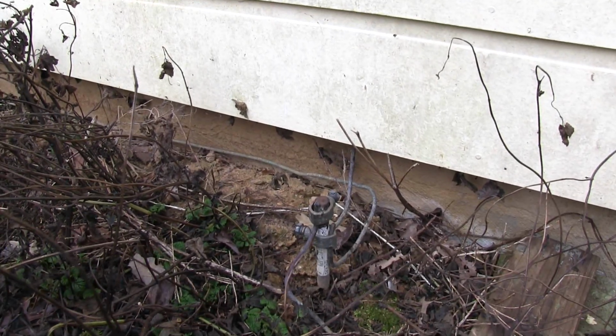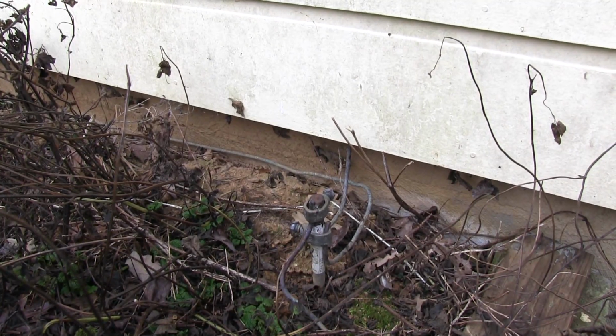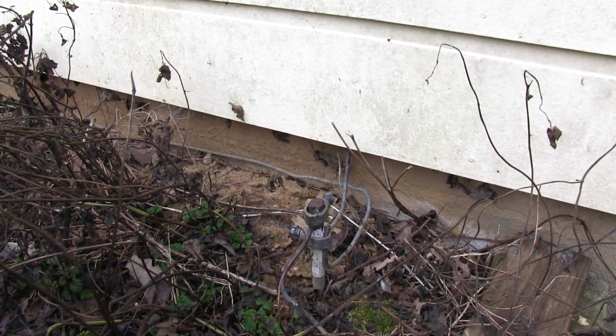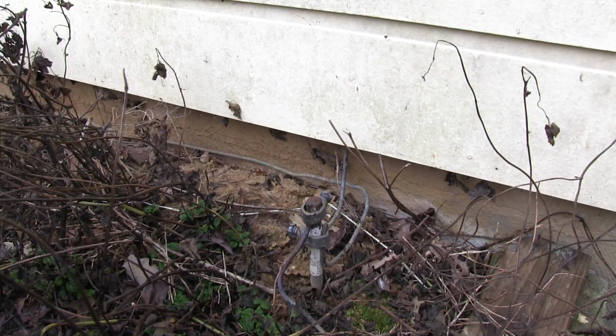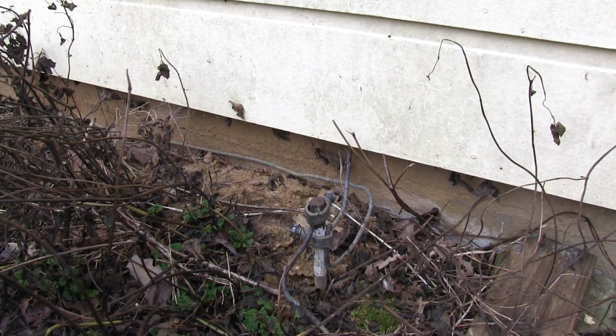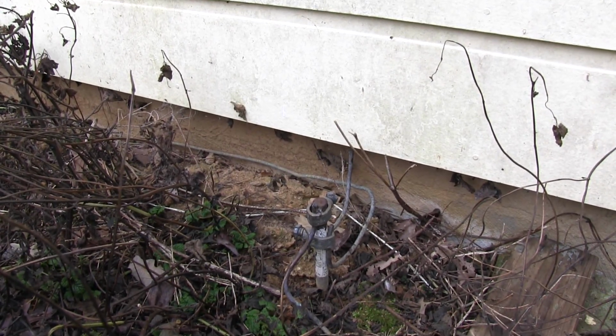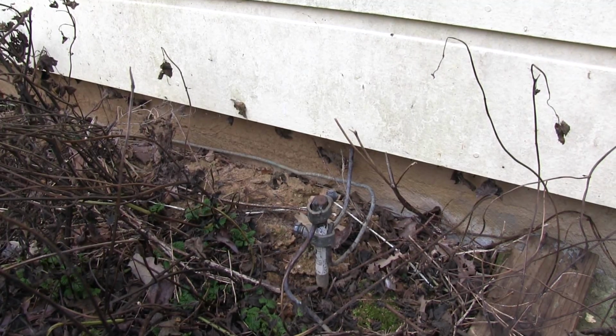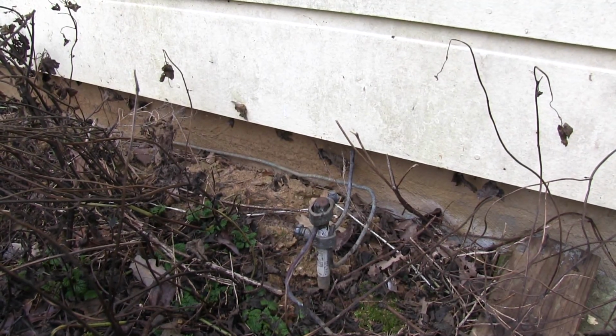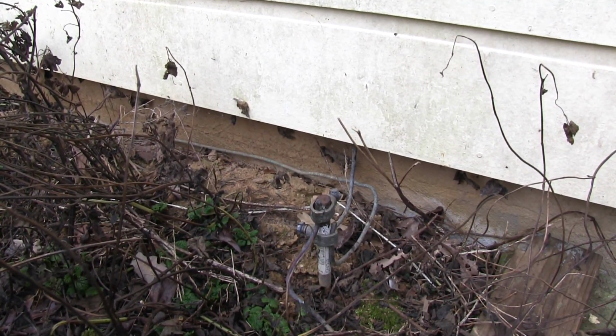When I first moved here, there were no ground rods on the fuse panel or circuit breaker panel. They had grounded the circuit breaker panel to the plumbing of the house, and the plumbing was plastic. It had one metal valve right near the fuse box, and that's what they grounded.